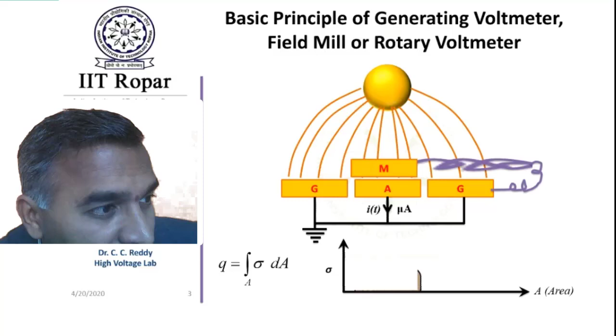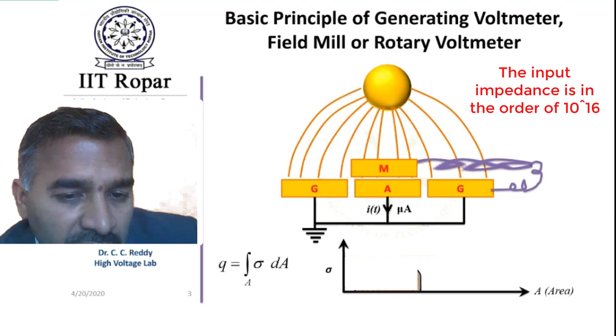In the electrostatic voltmeter you are measuring deflection, which is force based. The basic principle of a voltmeter is that it should draw very little current when connected to the measuring system. Here the input impedance is very high because this is a capacitive system, just like the electrostatic voltmeter—it's simply open circuit and capacitive impedance. So the input impedance is high and the loading effect is less, unlike resistive dividers, which take more current.